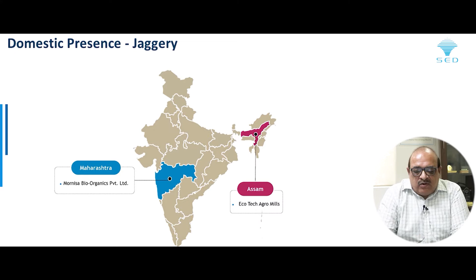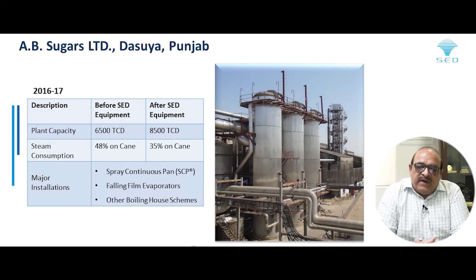Here is a concise list of installations where we achieved remarkable reductions in steam consumption. For example, at AB Sugars Limited, Dasuya, Punjab, in 2016-17, we reduced steam consumption from 48% on cane to 35%, which also led to an increase in crushing capacity. The major installations included spray continuous pan, falling film evaporators, and other boiling house schemes incorporated to achieve such targets.